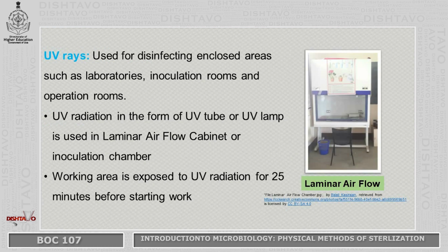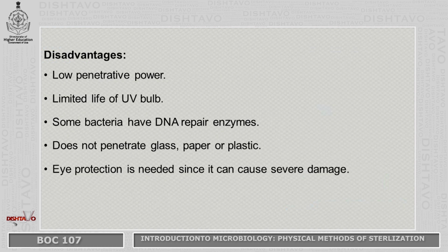Now UV rays are used for disinfecting enclosed areas such as laboratories, inoculation rooms and operation rooms. A UV tube or UV lamp is used in a laminar airflow cabinet for the inoculation chamber. The working area is exposed to UV radiation for 25 minutes before starting the work. This is the image of the laminar airflow.